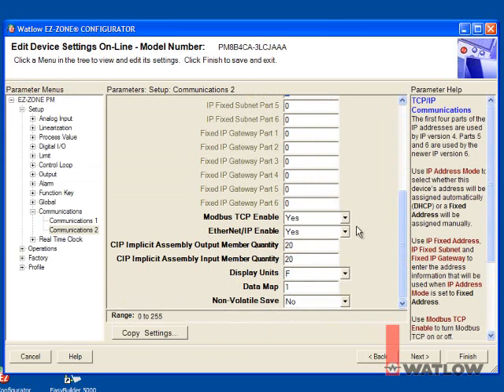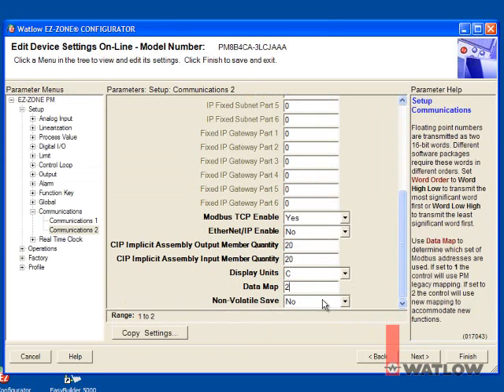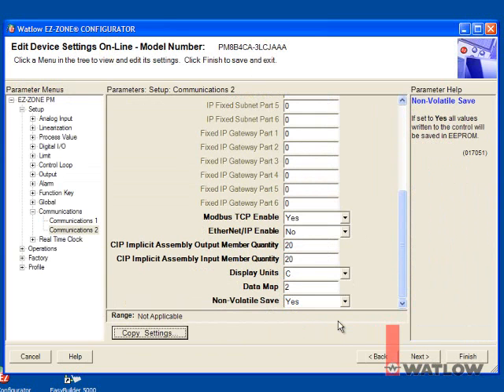Select the second controller and set it up the same way as the first, except for the IP address, which we'll set to the next available value. You may want to use EZ-ZONE Configurator to set up other parameters in the controllers for your application, such as input type and set point, but for this example we're done. Close EZ-ZONE Configurator, then cycle power to the PM controllers to make the IP address change take effect, and launch EasyBuilder 5000.